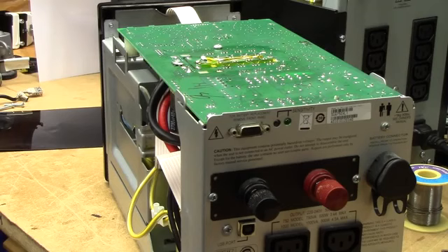Now, a downside of this modification is that I haven't figured out how to get the actual UPS capability working on it. Since these are line interactive UPSs, they have a constantly running AVR functionality to them. So the high voltage side is actually always connected to the grid, and it's monitoring the output of a transformer and using it as an auto transformer to boost or buck the voltage in case you have some surges or sags on your grid. Since we are using two transformers and one is just connected up basically as a single transformer with the only exception of the actual output winding, there's going to be some discrepancy.